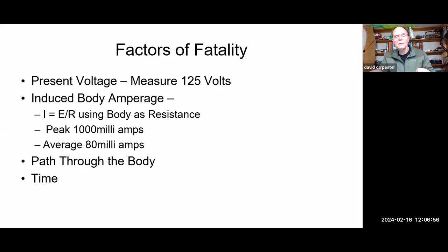There have been studies done on muscle contraction, measured in milliamps. So 1 to 5 milliamps, for example - your ground fault circuit interrupter at home, at your bathroom sink, is made to trip within 5 to 7 milliamps. If you have a 5 to 7 milliamp fault, it's going to trip out. But you can go into muscle contraction between 1 to 5 - that's the threshold where you can let go. At 10 to 40 milliamps, you can't let go. By the way, we do a class on overcurrent protection, and there are different levels of ground fault protection called classes - class A, B, C - and they're based on the milliamp rating of which one can be used and which one can't.